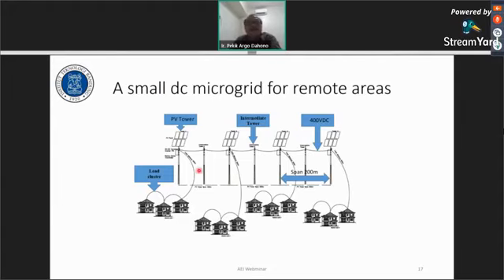However, to integrate many PV towers, we use a DC system, not AC. We chose 400 volt DC, similar to the voltage level already proposed by several countries. Because it's DC, it's easy to integrate several PV towers — we don't need to synchronize the frequency, so we don't need a communication system among the towers, and we have no problem with reactive power.